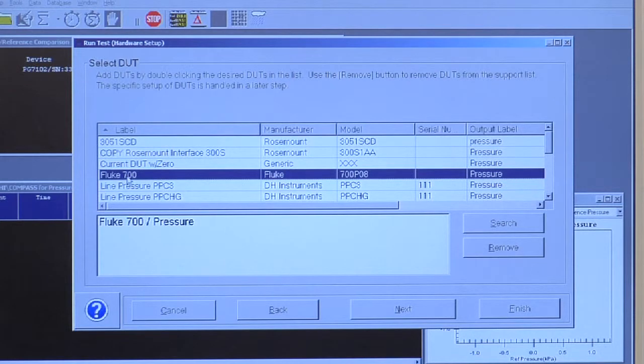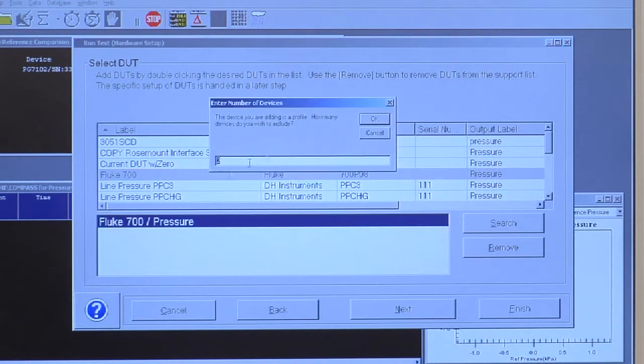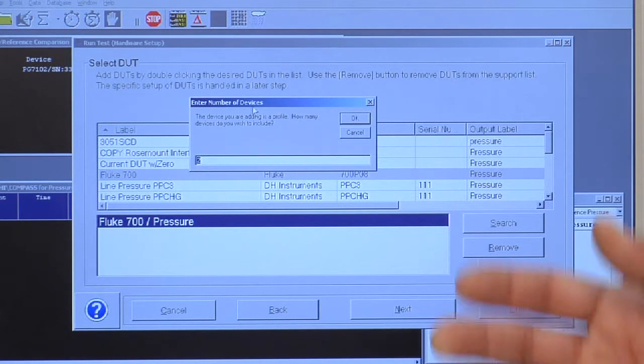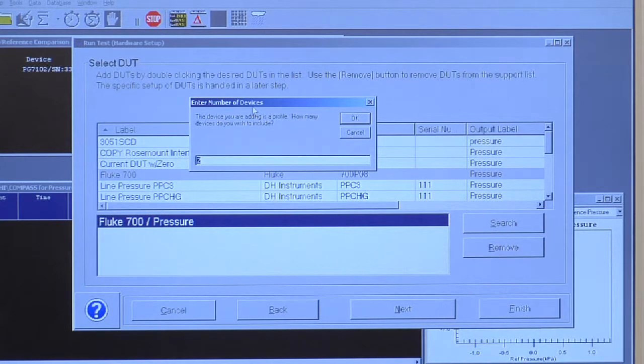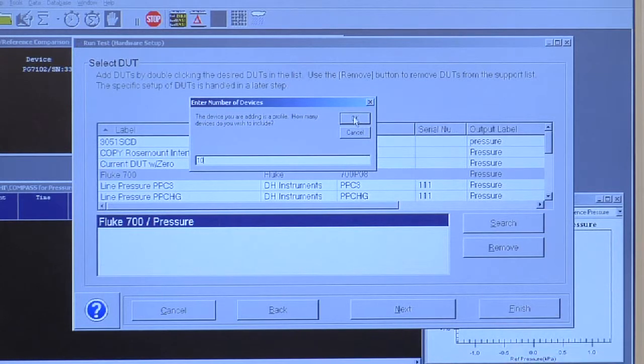Compass does support batch calibration. This instrument is set up as a profile. If I double click it again, I can enter in as many instruments that I physically have set up. If I have 10 pressure modules and 10 calibration adapters, I can type in 10, and now I have 10 instruments set up and I can complete my test that way.